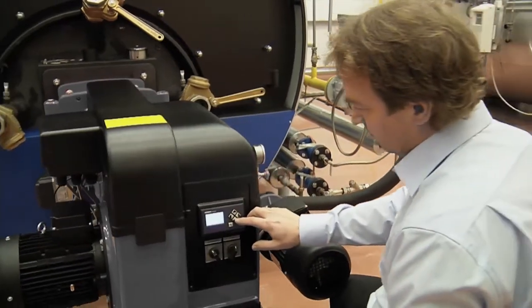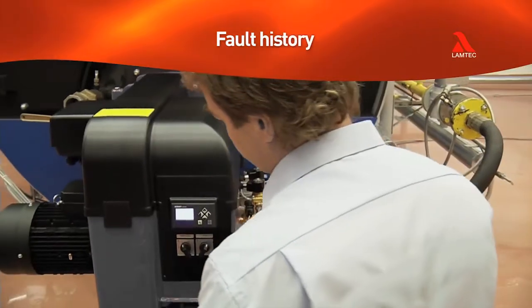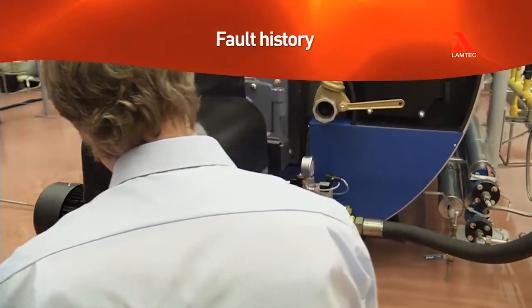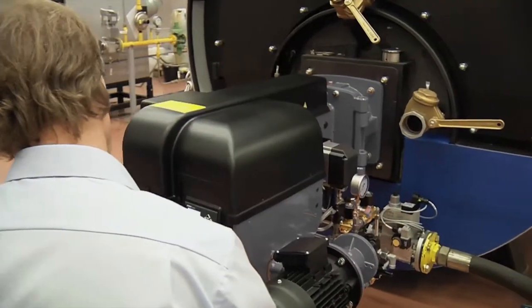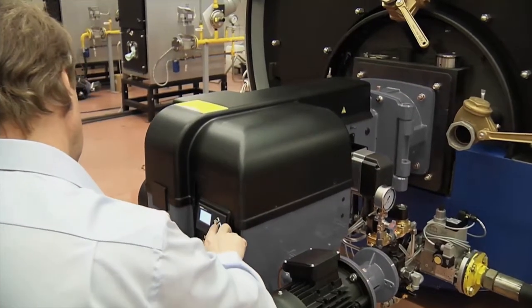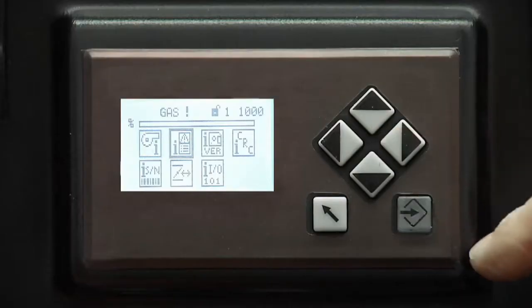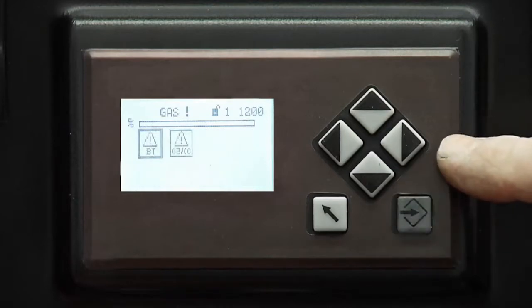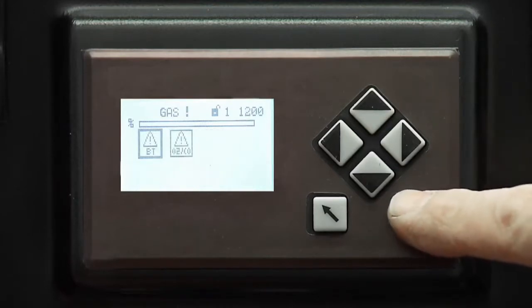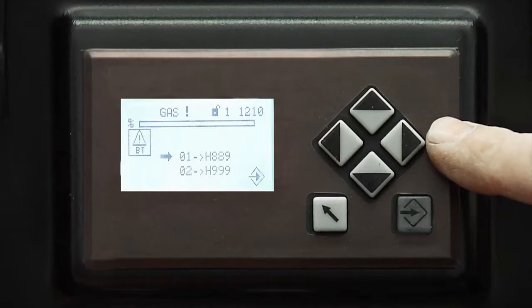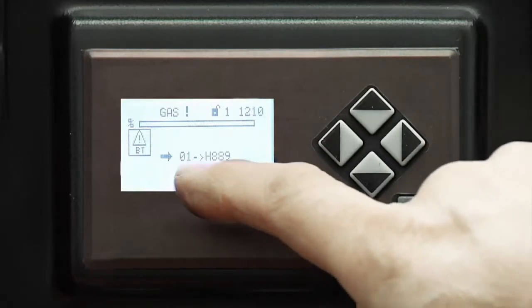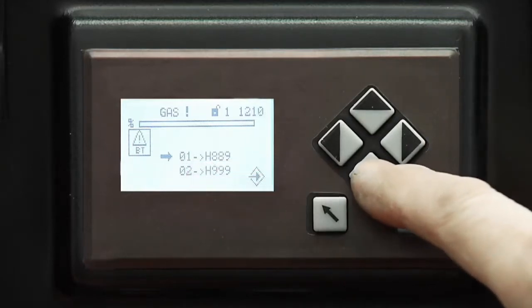The fault history menu is important for all burner operators. The error code in the history list will indicate the fault that has stopped the burner. Access the menu by pressing Enter. You will find an icon for the control unit, and pressing Enter there again will open the fault history. The display shows last 10 faults.